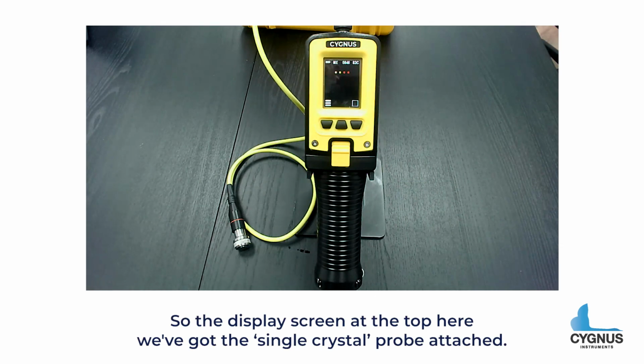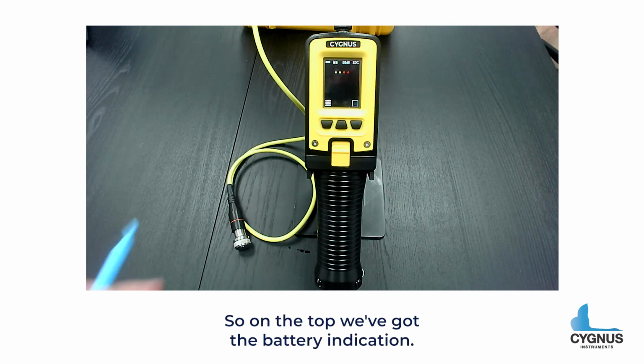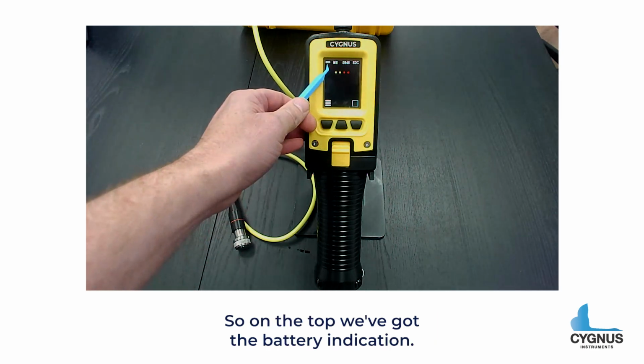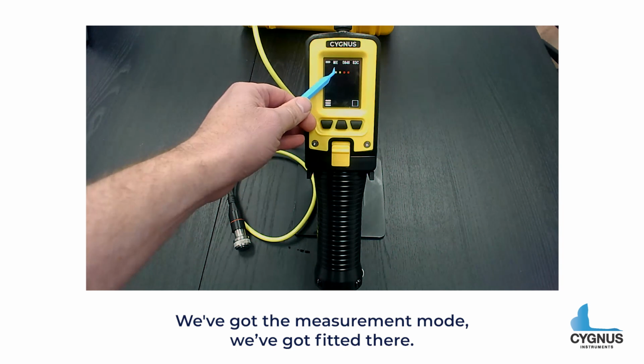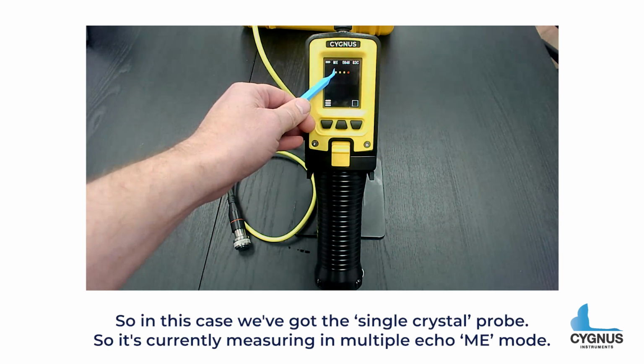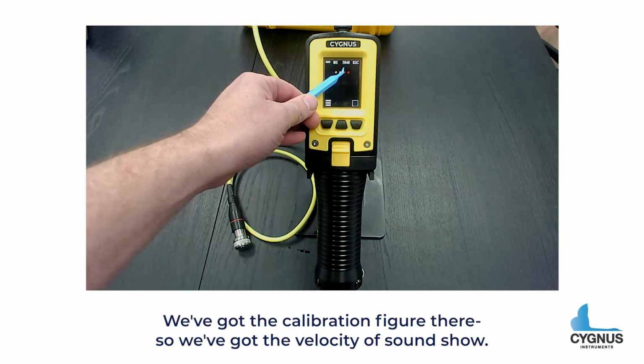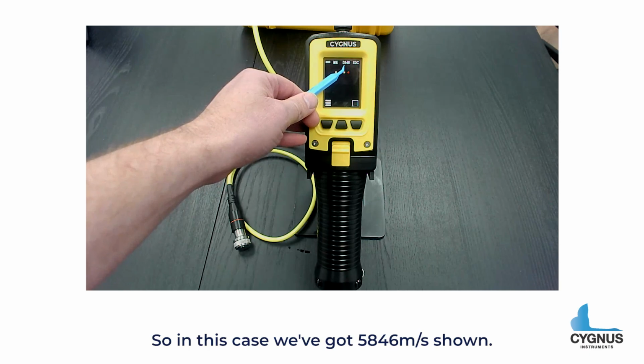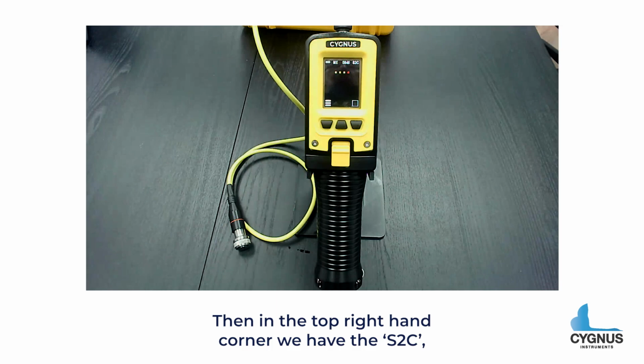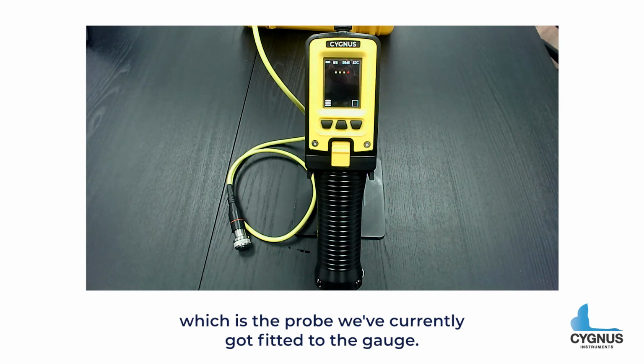So the display screen up the top here, we've got the single crystal probe attached. On the top, we've got the battery indication. We've then got the measurement mode we've got fitted there. In this case, we've got the single crystal probe, so it's currently measuring in multiple echo, ME mode. We've got the calibration figure there, so we've got the velocity of sound shown. In this case, we've got 5846 meters per second shown. And then in the top right-hand corner, we have the S2C, which is the probe we've currently got fitted to the gauge.